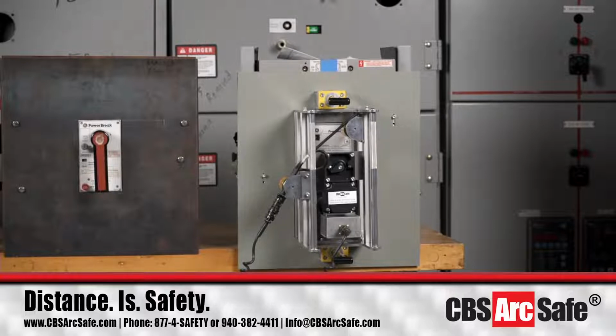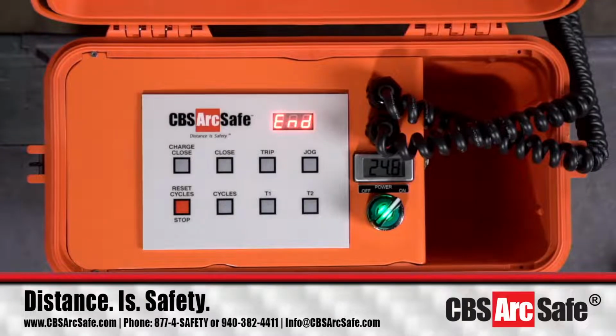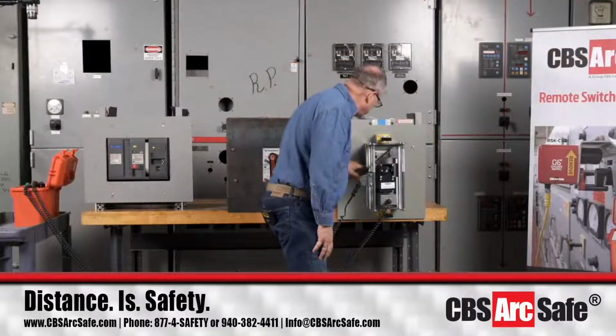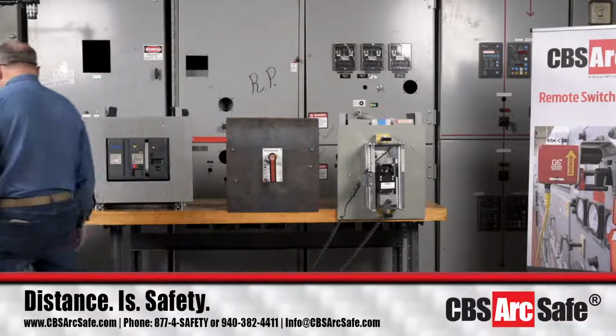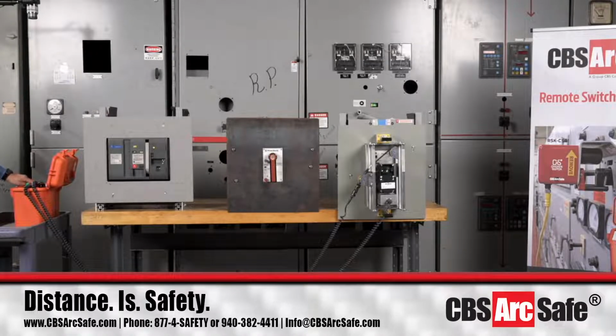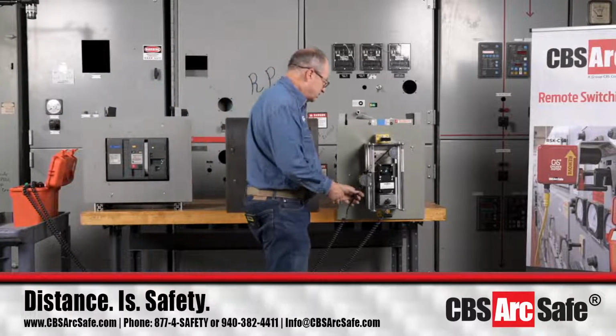Okay, so we've got this set now, so we hit charge close. And you hear that the spring is charged now. We can verify that real quick just by checking and taking a look on the face here. Okay, and we do have that indication. So now we're going to hit the close button and the trip button. And that's the basic operation of the RSA 96.1 AM.